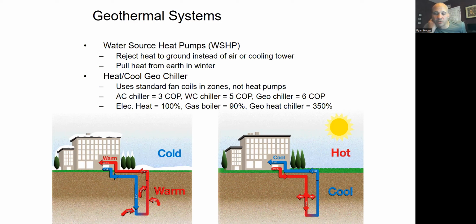Yeah, you could definitely make the bore fields bigger or put more of them in, but now you just need more space and more drilling costs, and most people have taken the choice of balancing that off and saying, nah, let's just do the base amount of wells, which means the amount of wells it takes for the smaller load of the heating and cooling. Whichever one's smaller, you put in enough of a well field for that. And then your other heating source or cooling source takes care of the gap between those. That's more common because it's a better first cost standpoint. And you get almost all the energy benefits of the geo, and you drop the first cost a lot.